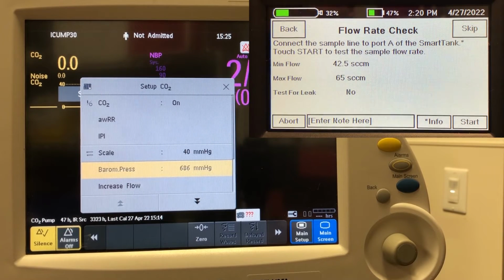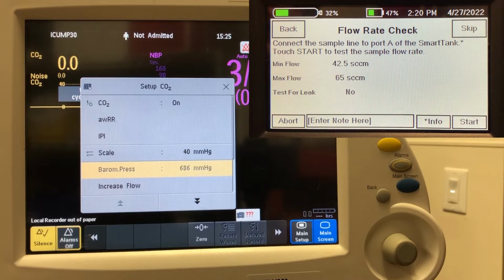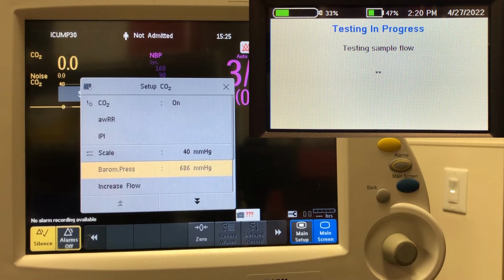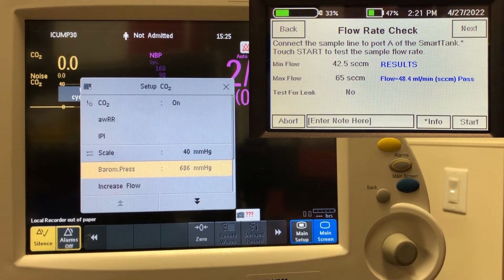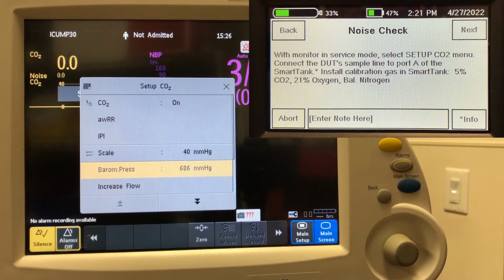Okay, next we're going to check the sample flow rate. So we connect this sample line of the extension module to port A of the Smart Tank, and we hit start. Now in our simplified test sequence, we would connect the exhaust line as well, and it would allow the Smart Tank to measure any internal leak in the system, which makes the test process much faster. But in this case, it only measured the flow. It's well within the pass criteria. We can move on. In this next test, we're going to check the noise.